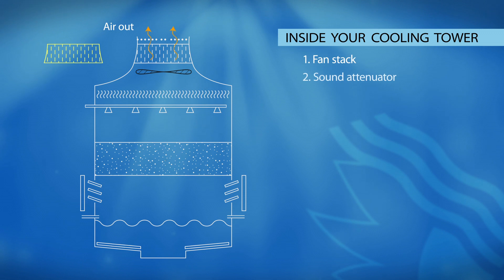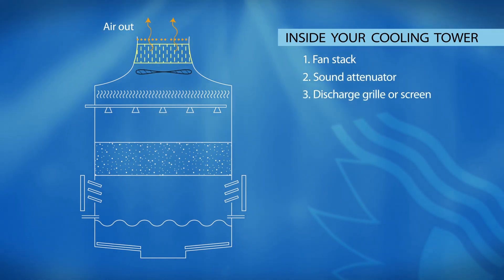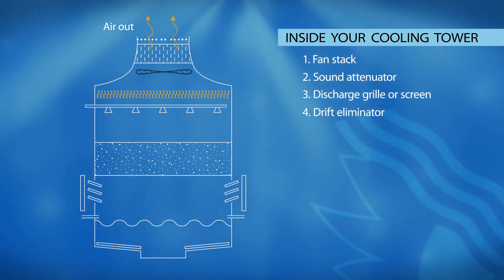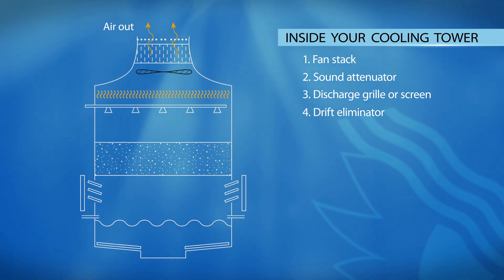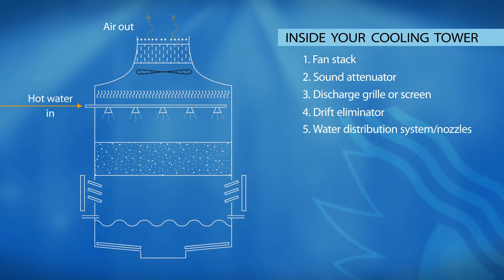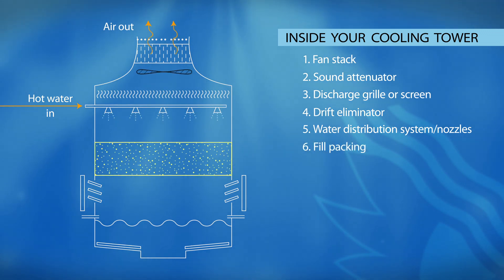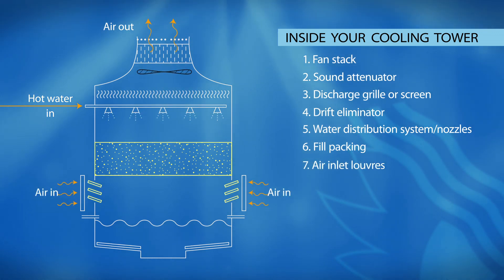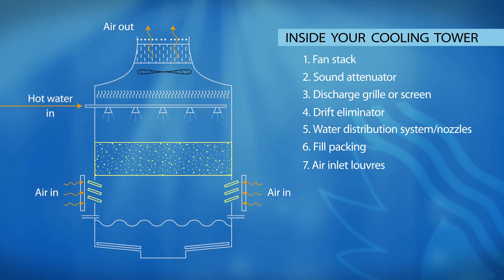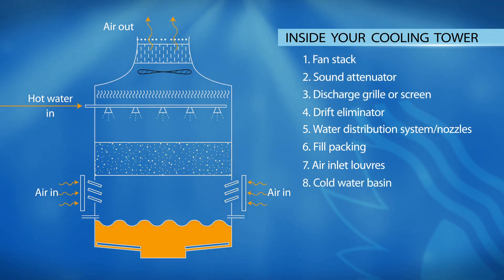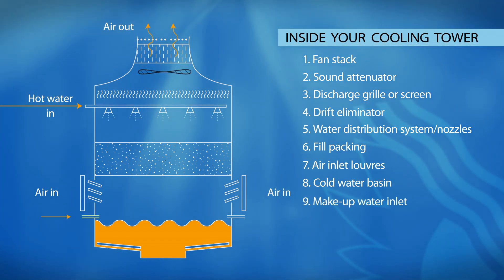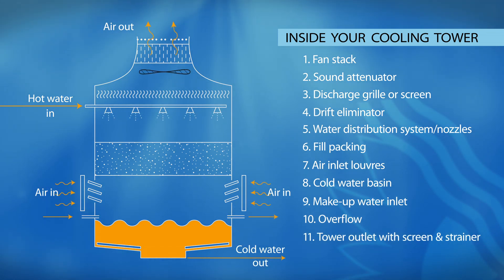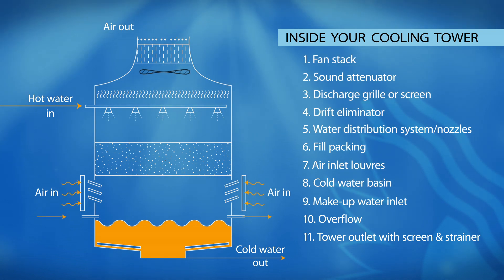They include a fan, sound attenuation, and discharge grill or screen. The drift eliminator reduces the number of water droplets that leave the tower trapped in the tower discharge air. The tower also features a water distribution system where hot water comes from the process or building and is sprayed over the fill where evaporation takes place. Around the cooling tower, air inlet louvers allow cold, dry air to flow over and through the wet fill. The cooled water is collected in the basin, which has a make-up water inlet and overflow outlet.